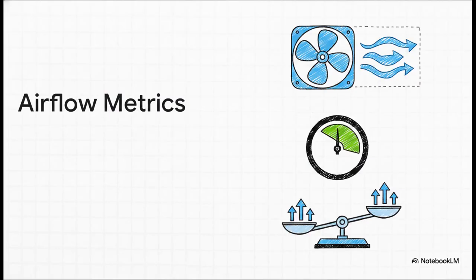Beyond just the physical size of the tubes, we measure and calibrate the airflow using these technical metrics. We ensure proper CFM, which stands for cubic feet per minute, so the exact right volume of air is distributed to the right places. We also balance the static pressure, which, if you think about it, is essentially the blood pressure of your HVAC system.